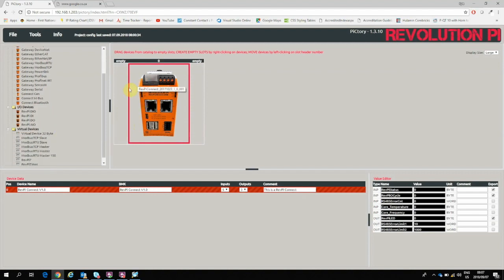Next, it's important to remember that you need to assign modules in Pictory in the same order that they are physically connected to the device. So what I physically have connected right next to the RevPi Connect is the Analog Input and Output Module, which is over here under IO Devices.